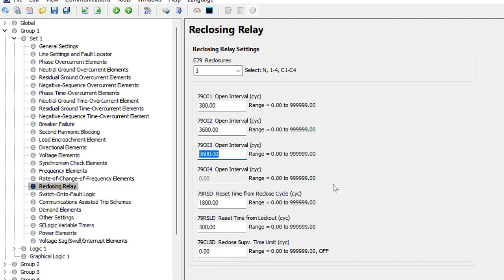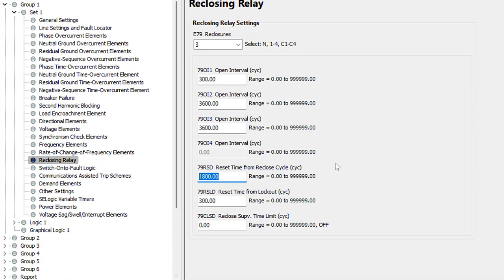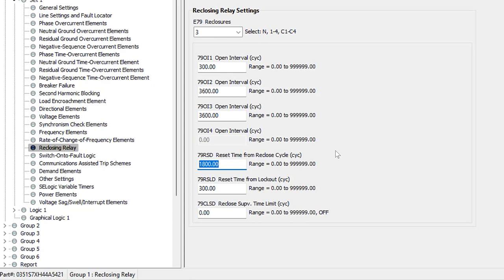We also need to program three additional timers. The first is 79RSD — the reset time from the reclose cycle. This is the time the relay waits to return to the reset state after a successful reclose attempt. If the relay recloses automatically and holds without tripping again, after 1,800 cycles — 30 seconds — it goes back to the reset state and is ready to go through the sequence again. I'll leave that at the default of 1,800 cycles.